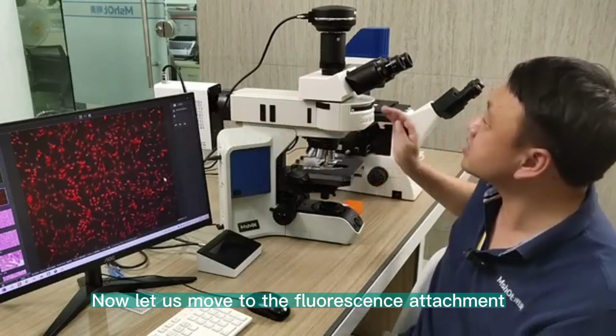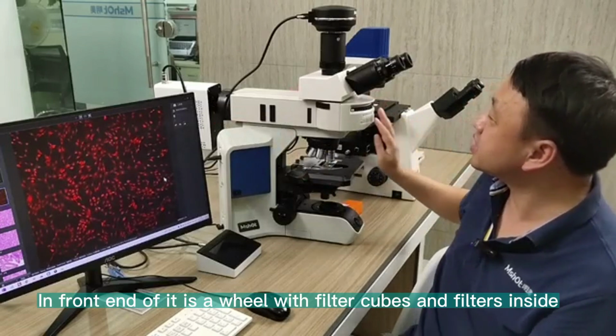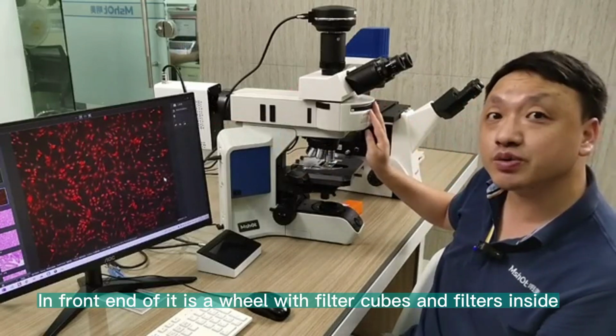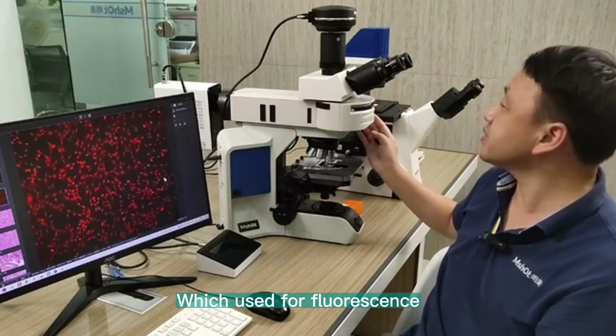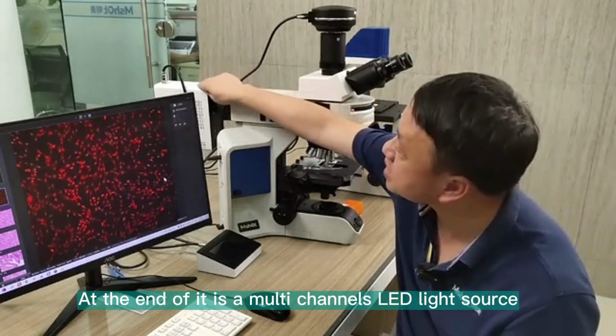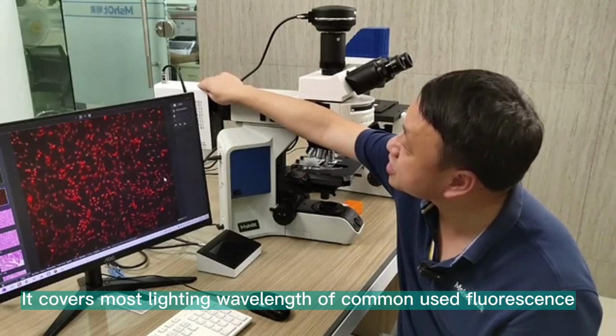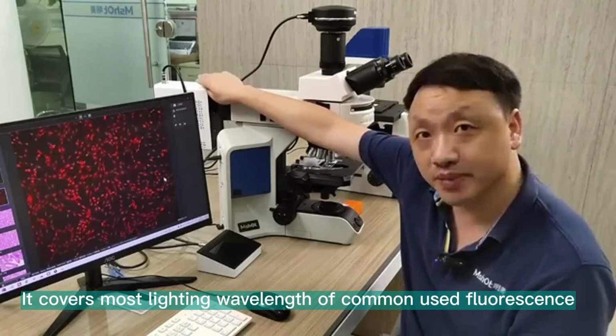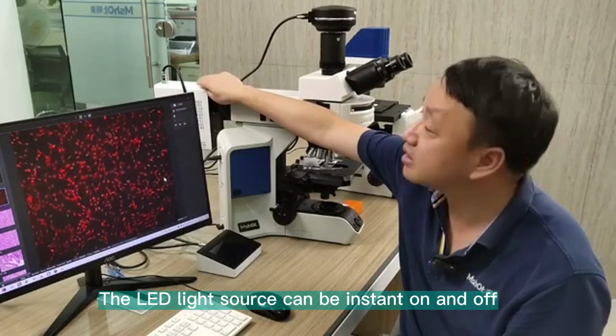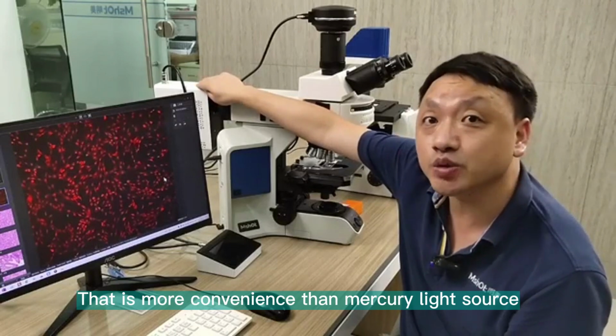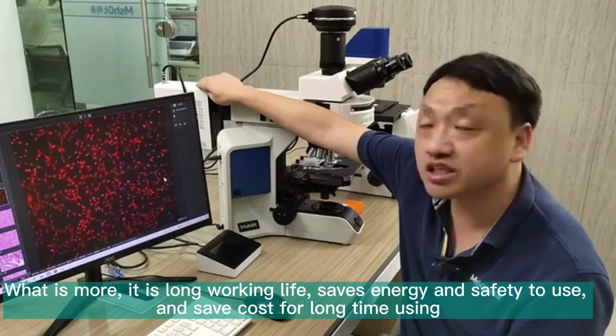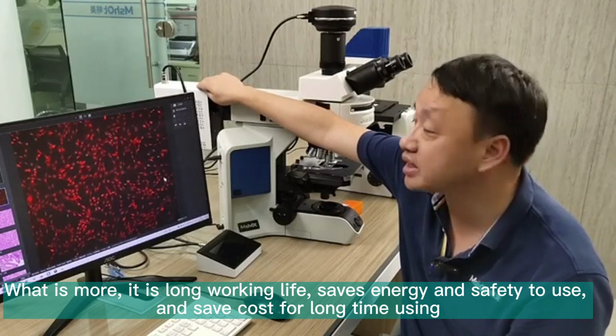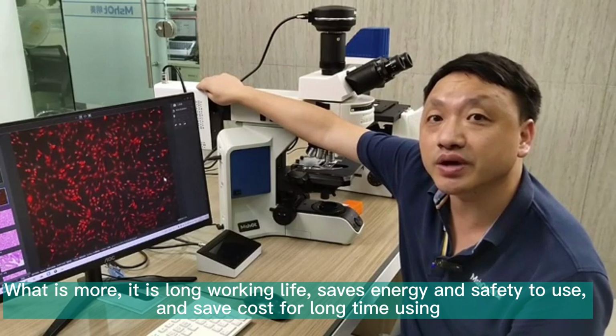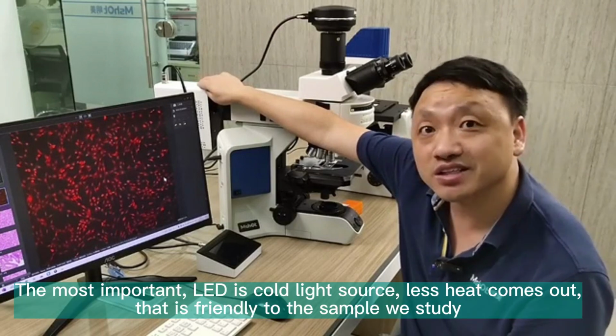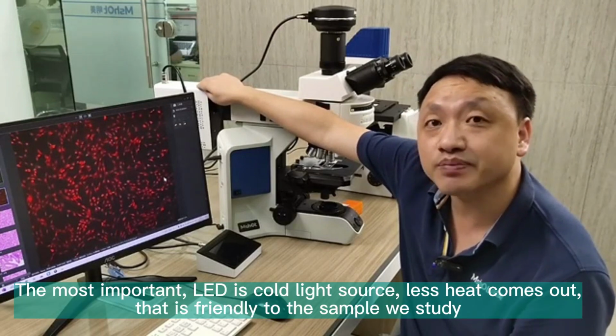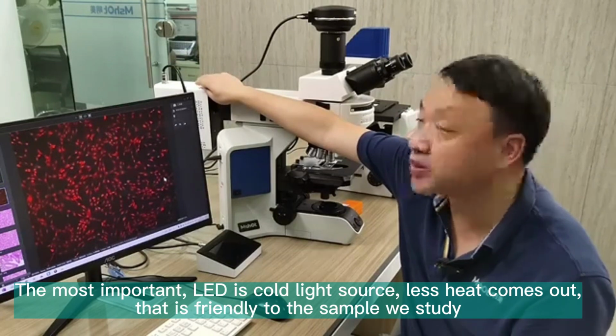Now let us move to the fluorescence attachment. At the front end of it is a wheel with filter cubes and filters inside, which are used for fluorescence. At the end of it is a multi-channel LED light source. It covers most lighting wavelengths of commonly used fluorescence. The LED light source can be turned on and off instantly. That is more convenient than a mercury light source. What is more, it has a long working life, saves energy, is safe to use, and saves cost over long-time use. Most important, LED is a cold light source. Less heat comes out. That is friendly to the sample we study.